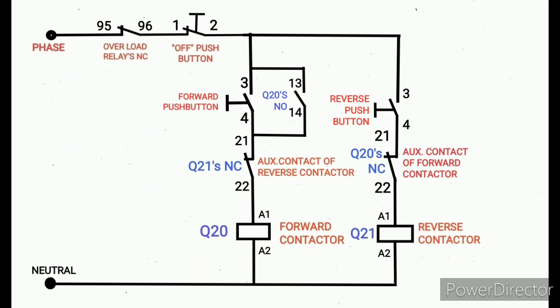Next we are going to draw the reverse push button hold on, because this is also momentary type. The reverse push button hold on and the reverse contactor Q21's auxiliary contact NO 13 and 14. This auxiliary contact is directly parallel with reverse push button.